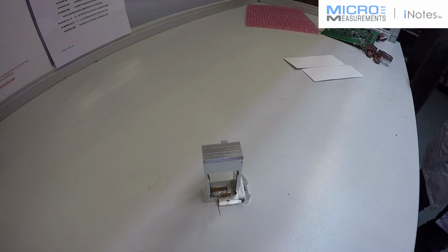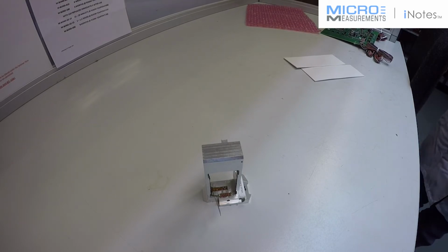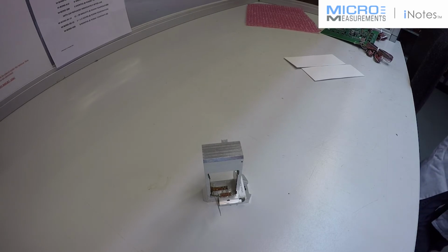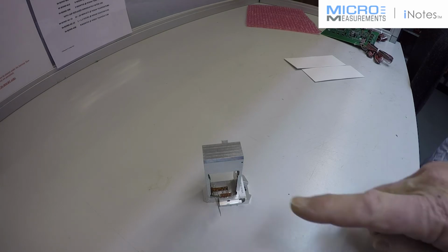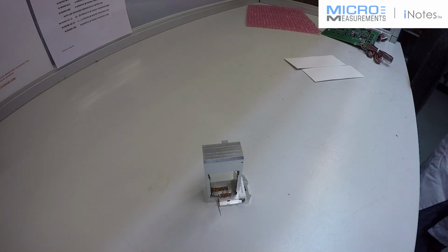And again, the temperature here is what, ambient most of the time, is it? Yeah, absolutely. There's no temperature compensation required on this. It just works as a standard ambient temperature. Full Wheatstone bridge, yes? Yep. Yes. And the cabling coming out, well, obviously the PCB board comes straight off onto there, but how do you test to see if this is working? When you've got the flex circuit, we've got a mating connector we use, which we can connect into our DVM power supply and check balances and resistances and the insulation of the installation.